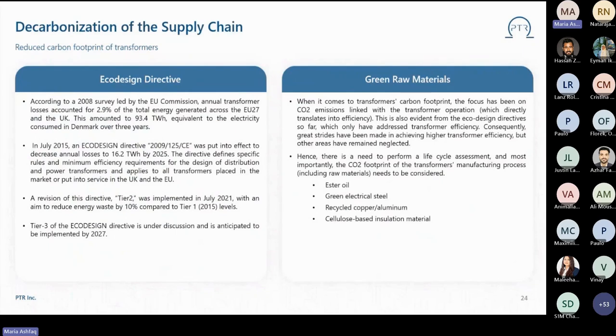In order to reduce these energy losses from 93.4 terawatt hours to 16.2 terawatt hours by 2025, an Eco Design Directive was put in place in July 2015. This directive specifies rules and minimum efficiency requirements for both distribution and power transformers, applying to all transformers placed in the market or put into service in the UK and EU. However, I'd like to highlight that this directive does not apply to the already existing installed base of distribution transformers; it only applies to new transformers coming into the market.